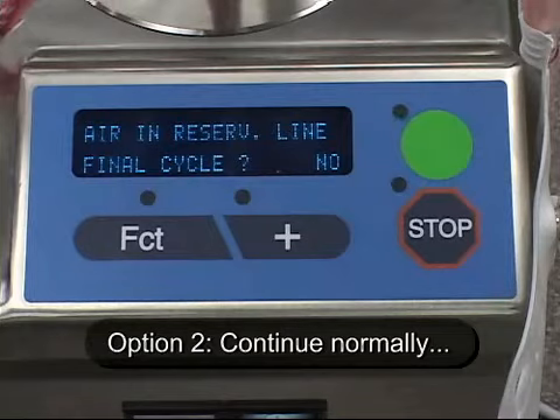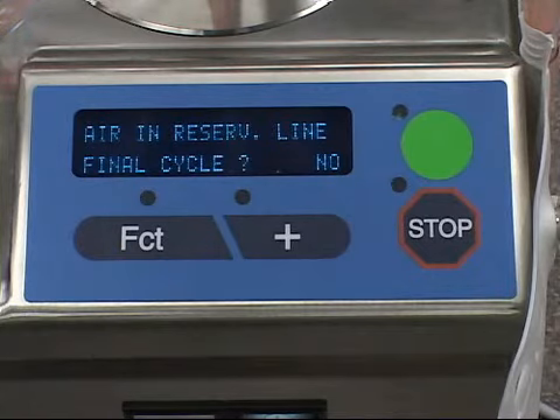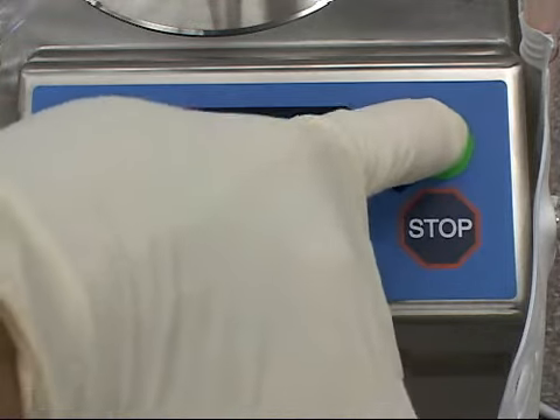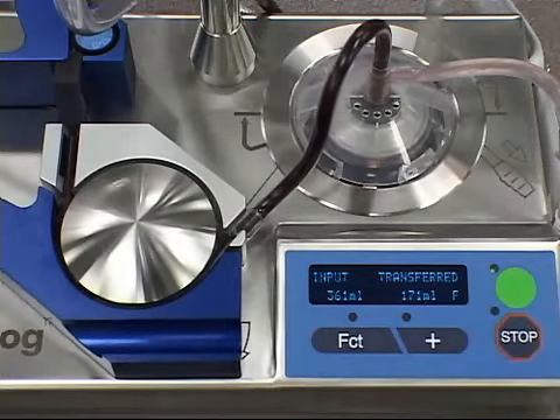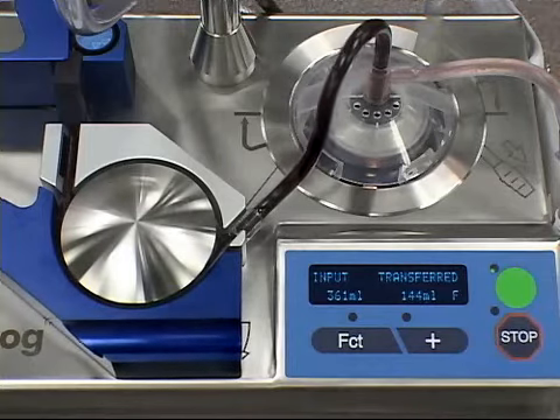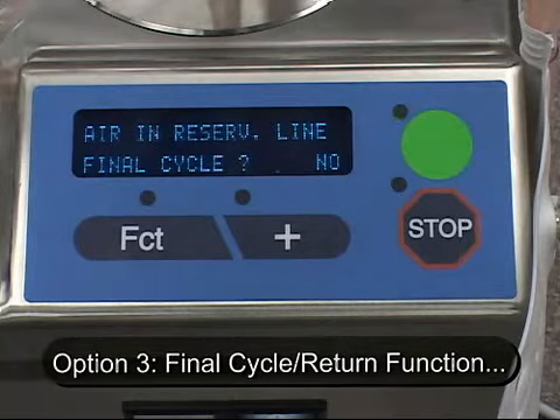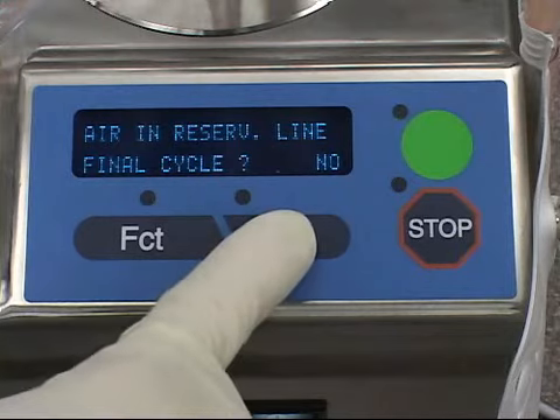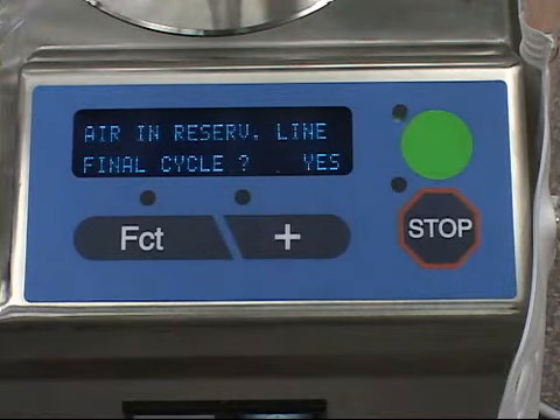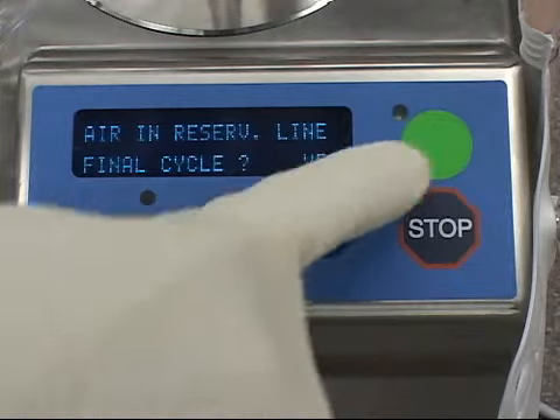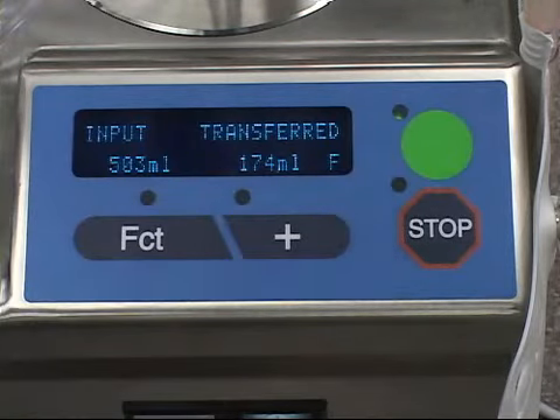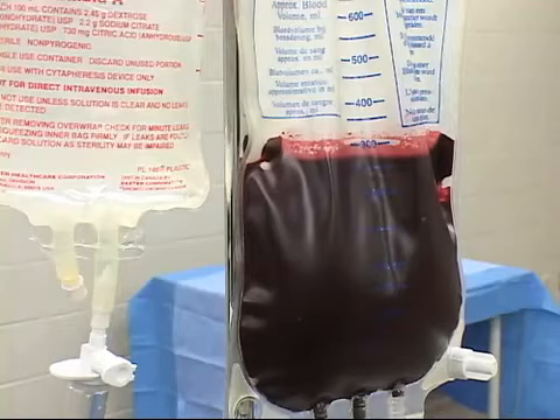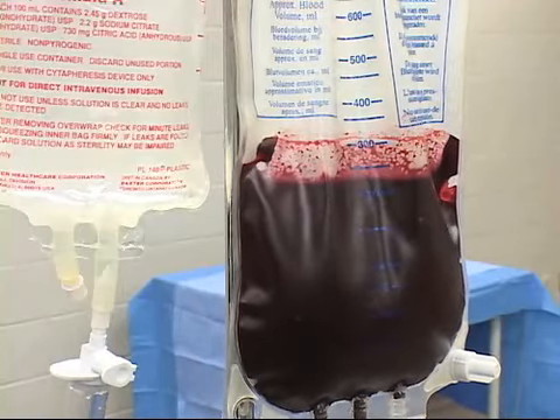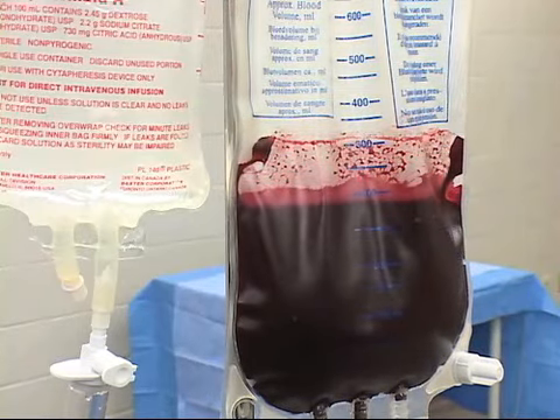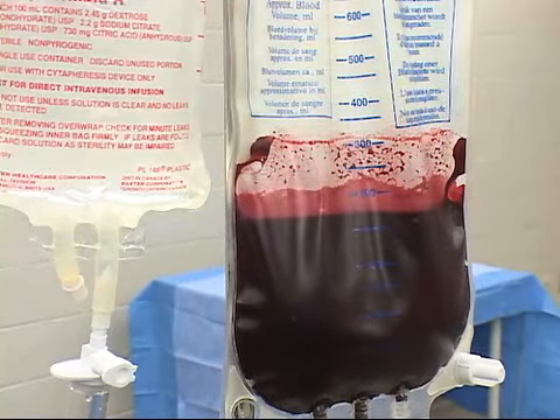Number 2. Continue normally. This option is usually used to restart the fill phase when there is a false air detect. Press the Go key. A normal cycle fill phase is attempted. Number 3. Final cycle, return function. Pressing the incrementation plus key to display yes, followed by the Go key, confirms that this is the final cycle for blood processing. The machine will then finish filling a partially filled bowl by drawing previously washed red blood cells from the holding bag and starting the wash phase of the cycle. This process is called concentrate.